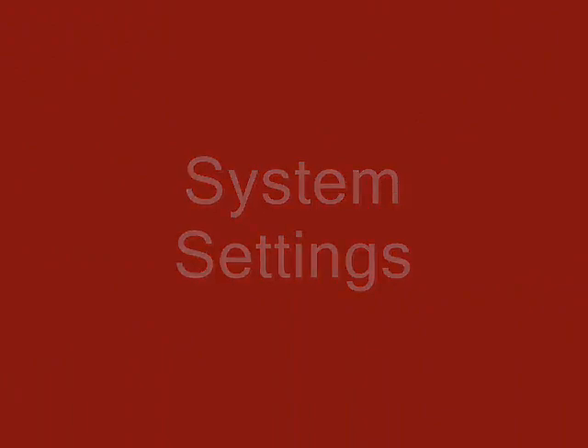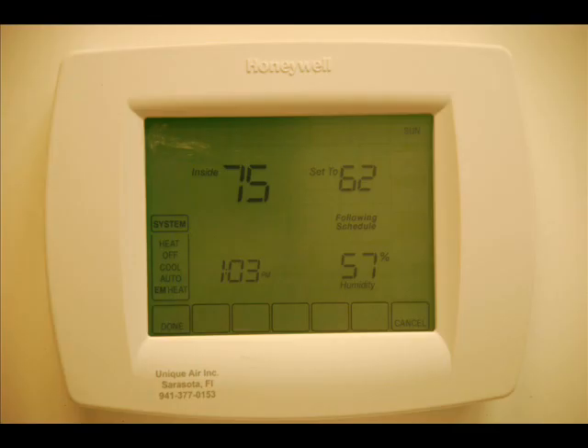System settings. Press the System button repeatedly to toggle through system setting choices. In Heat, the thermostat controls only the heating system. In Off, the heating and cooling systems are off. In Cool, the thermostat controls only the cooling system. And in Auto, the thermostat automatically selects heating or cooling depending on the indoor temperature. If you have a heat pump with auxiliary heat, choose Em Heat or Emergency Heat to activate it. In this mode, the compressor is not used.